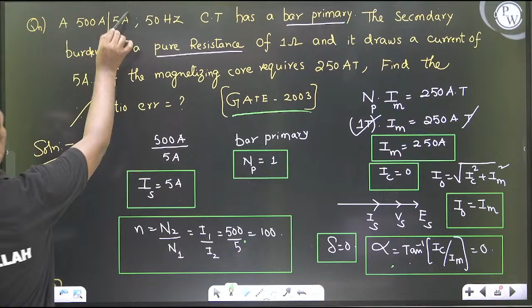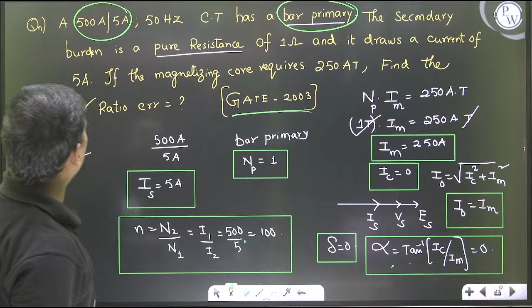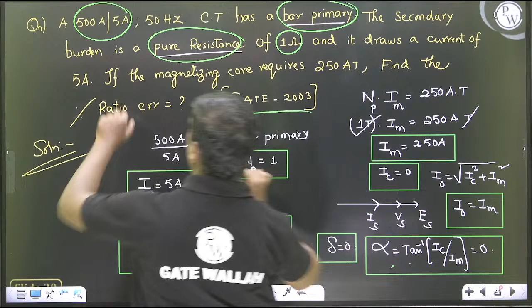A 500 amperes by 5 amperes 50 Hz current transformer has a bar primary. The secondary turn burden is a pure resistance of 1 ohm and it draws a current of 5 amperes. If the magnetizing core requires 250 ampere turns, find the percentage of ratio error.